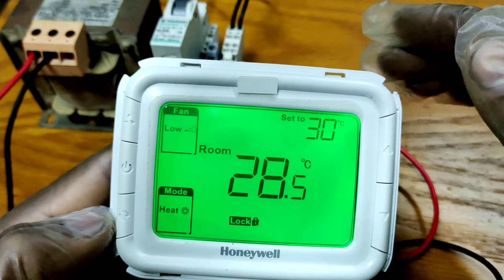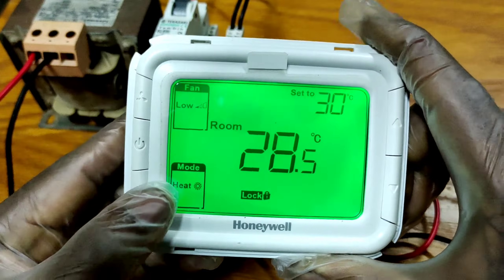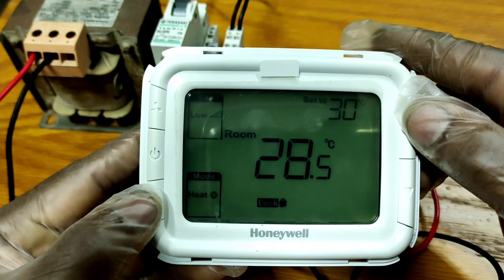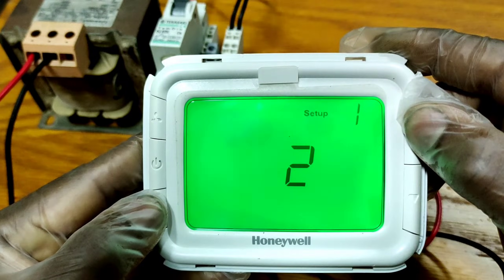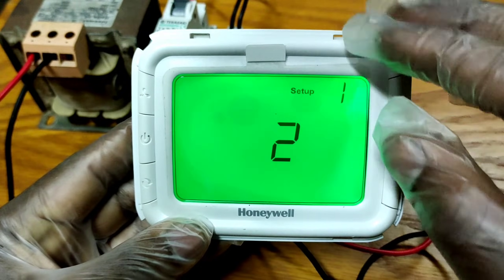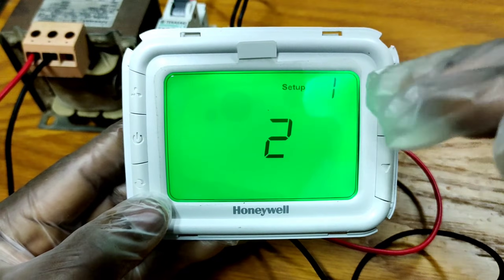In this situation, how we can unlock the keypad. You have to go to the installation setup. For installation setup, you need to press the mode button and the up push button together for at least three seconds. Press both buttons, then you will enter the installation setup. Now the setup number is one, and you have to go to setup number 2.